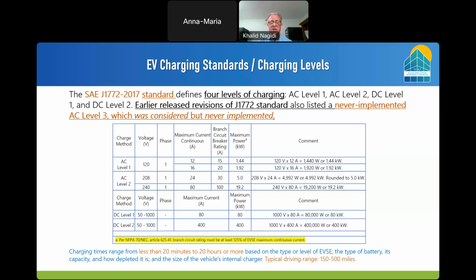On the right-hand side is a simple calculation. We know that the power is the voltage times the amperage, and it will give you the power in watts, and you convert that one to kW. AC level 2, 208 is for commercial here in North America, and 240 is for residential. So if we go with 208 and we have a circuit breaker of 30 amps, then the maximum current that you can draw is 24 amps. On the other hand, if you have 240 volt and you have a circuit breaker of 100 amps, then the maximum continuous current that you can draw is 80 amps. For the first one at 208, the maximum power is 5 kW, and for 240 it is 19.2 kW available power to charge your electrical vehicle.